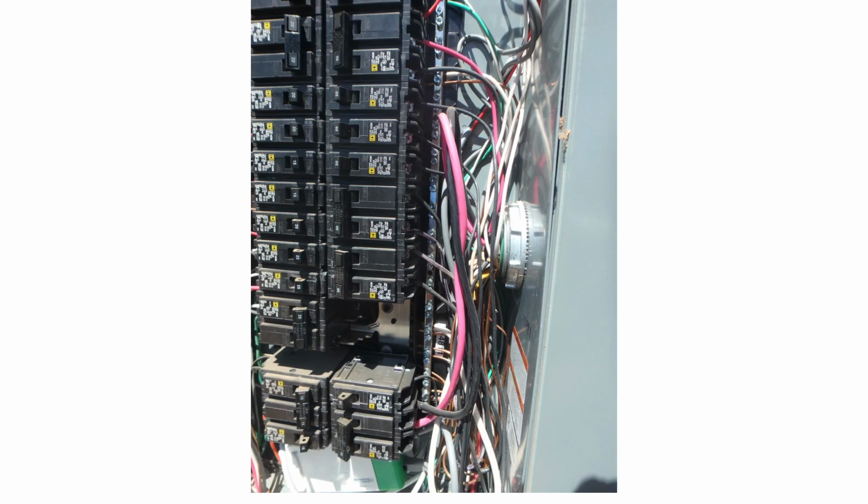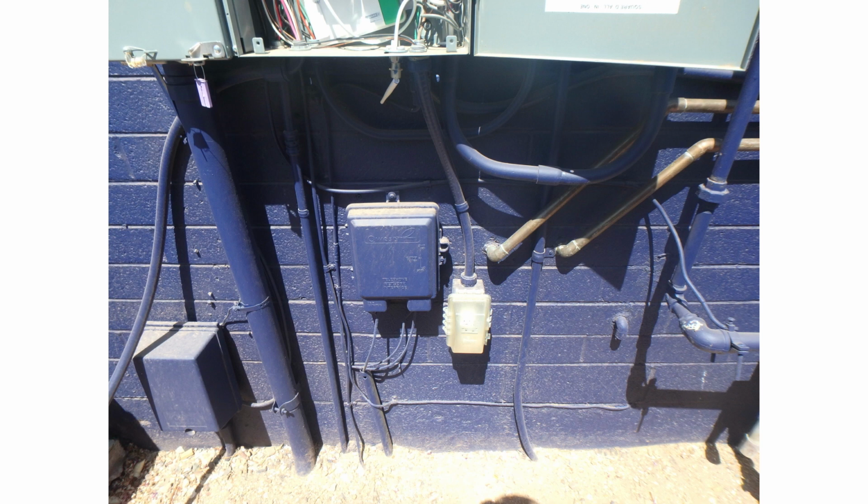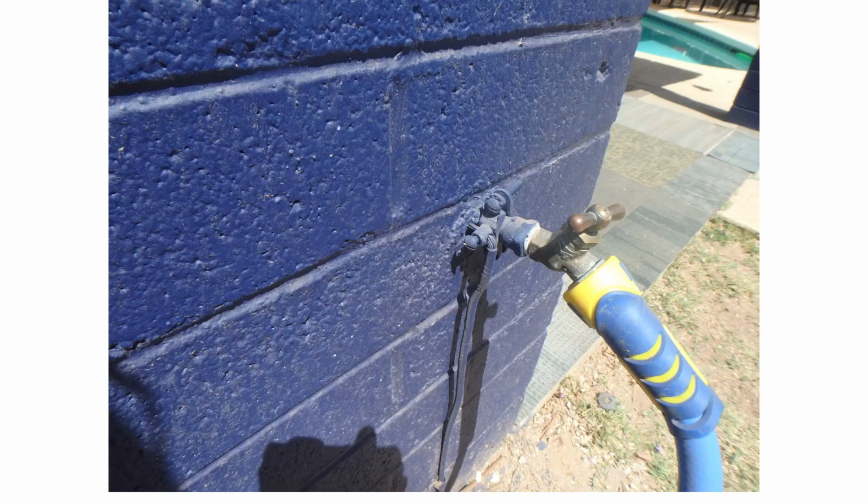Now electricity goes inside the house, eventually coming back to the panel, neutrals and grounds. So I'm going to look at the neutral and the grounding bars. And then I can follow that right to the grounding and bonding wires. As those grounding and bonding wires leave the panel, we can follow the ground as it disappears. And the bonds, in this case, are fairly easy to follow. Sometimes they aren't. Sometimes they just go in with the conductors inside those panels. Our water bond is actually diving down into the dirt and then eventually coming up at the hose bib down the way.